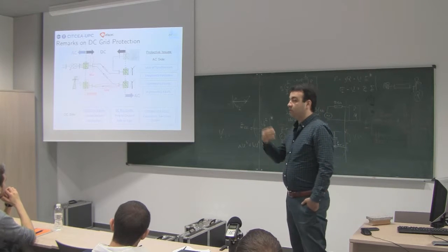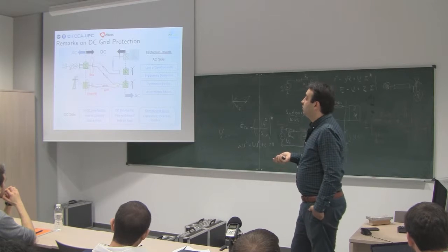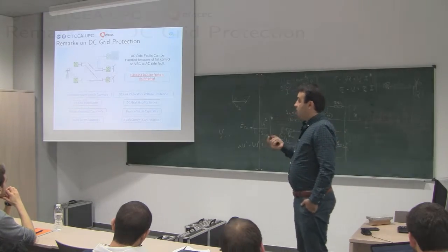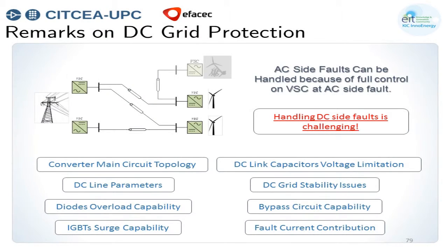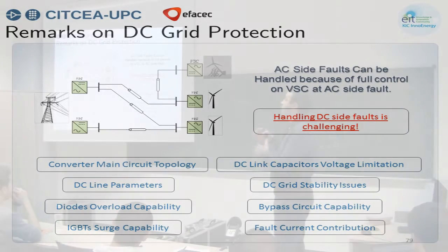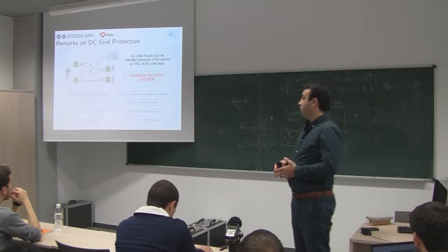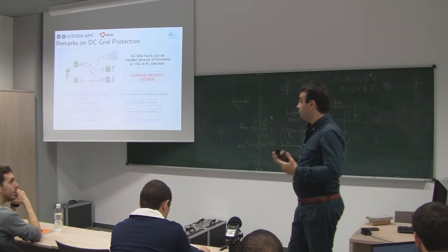Or you might have some kind of internal fault in the converter, in components like capacitors, IGBTs and diodes, which can affect the DC side of the converter. So these are the issues we should be aware of. Then, when designing the protection system for the HVDC grid, we should be aware of the characteristic of the fault current, the converter main circuit topology, DC line parameters, the anti-parallel diodes' overload capability, and the IGBT surge capability. We should also take into account the DC capacitors' voltage limitation, as well as the DC grid stability, which implies very fast detection and fast interruption. Also the bypass circuit and fault current contribution.